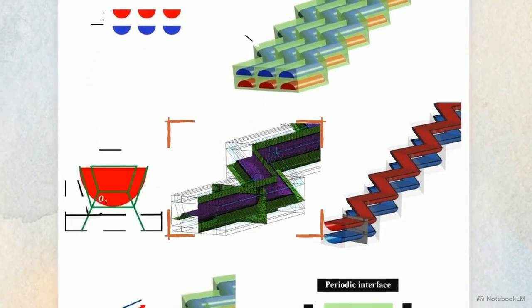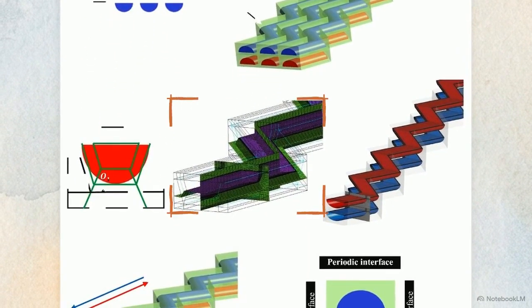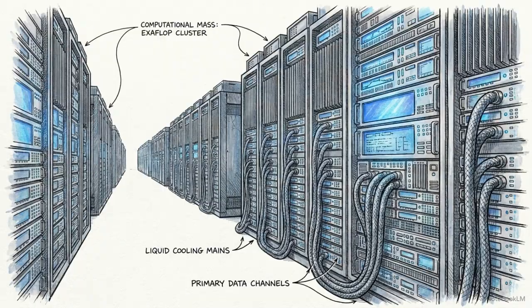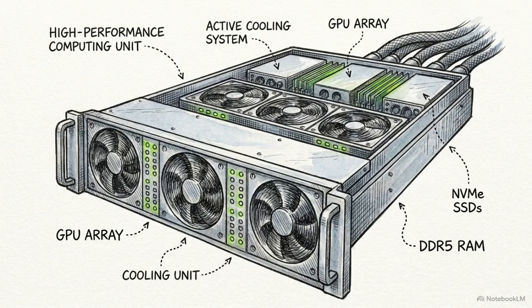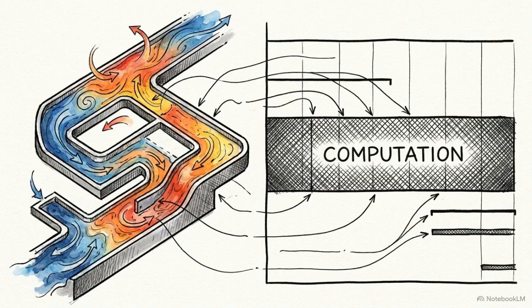To accurately map the fluid's micro-variations, the CFD solver requires high-resolution real gas property tables fed directly into the model. That level of accuracy carries a massive computational cost. A single high-fidelity simulation using shear stress transport turbulence models takes between 10 and 26 hours to run, and that timeframe assumes the simulation is running in parallel across 48 high-performance computing nodes. CFD provides perfect thermal visibility, but its computational weight makes rapid parameter sweeping and iterative design impossible.